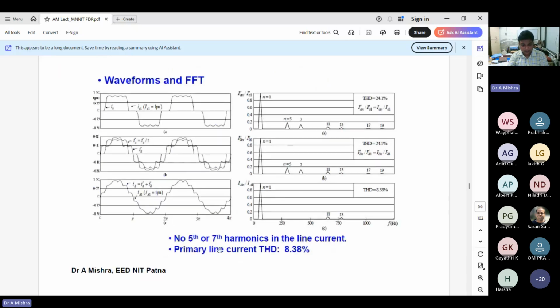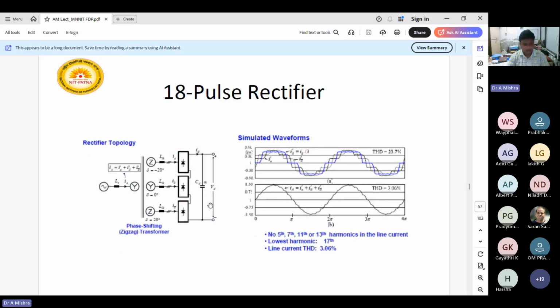Input current, output current, and primary line current THD is coming out to be 8.38%. It is also used for the reduction of the lower order harmonics, and lower order harmonics are dominant in nature. Filter design for the lower harmonics is very difficult. For the higher order harmonics, any LC filter can be designed, because higher order harmonics have low magnitude. The lower order harmonics have high magnitude, and that is difficult to handle by simple filters. So it is included in the converter itself that it will reduce the lower order harmonics by default.